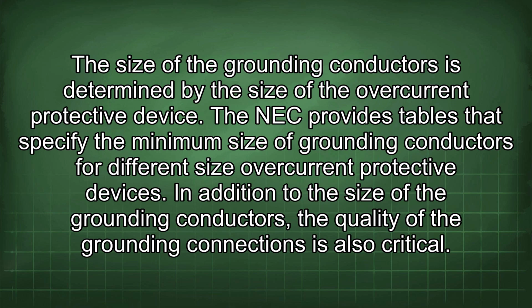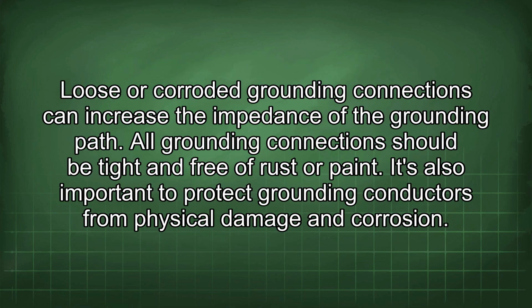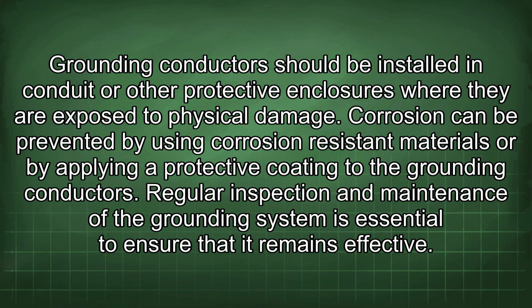In addition to the size of the grounding conductors, the quality of the grounding connections is also critical. Loose or corroded grounding connections can increase the impedance of the grounding path. All grounding connections should be tight and free of rust or paint. It's also important to protect grounding conductors from physical damage and corrosion. Grounding conductors should be installed in conduit or other protective enclosures where they are exposed to physical damage. Corrosion can be prevented by using corrosion-resistant materials or by applying a protective coating to the grounding conductors.